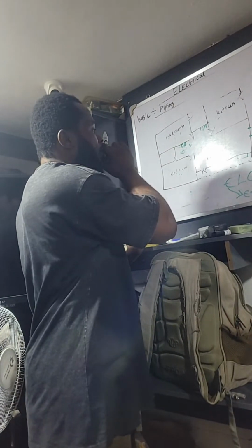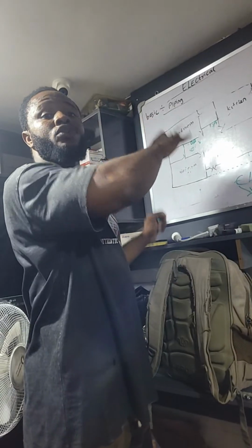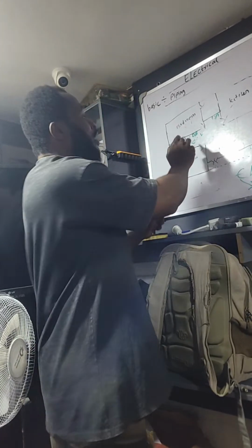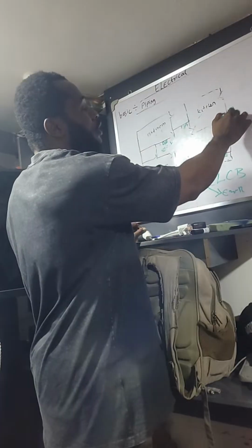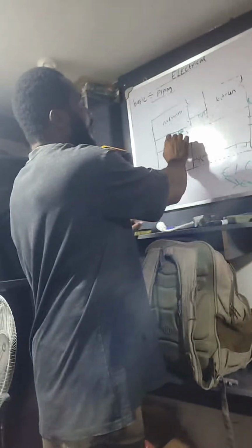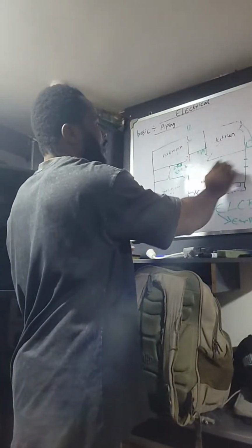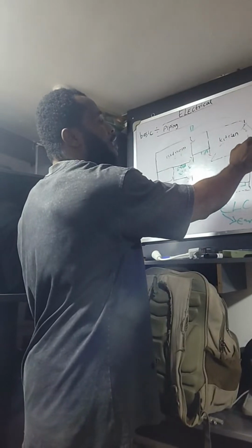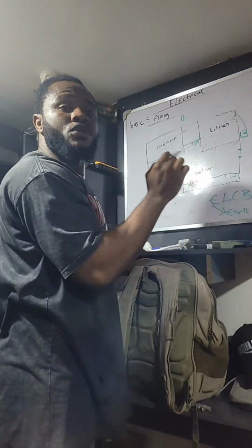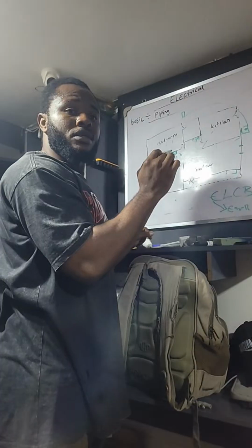If you observe very well, if this is a duplex, I think they call it duplex, then they have up and down. If this is a duplex and this is their junction box for drawing the load cable inside, what they will do is that this guy will have his ELCB here, the other guy up will have his ELCB. They will drag both cables, come to this side, then join them inside here, giving them a single supply. You understand?